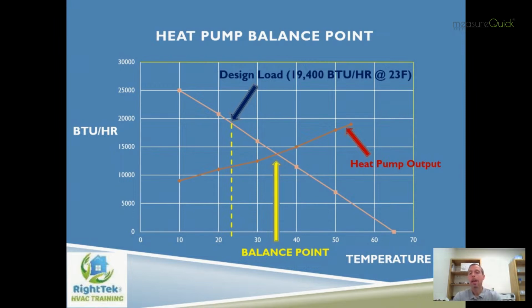But I also want to look at that heating performance. In my world, I always wanted a unit that not only fell within the sizing parameters given to me on the cooling side, but also would carry that home down on the heating side, preferably into at least the middle 30-ish range. Then I knew I would have a heat pump that was going to perform reasonably well and efficiently for both heating and cooling that house. And as Jeremy mentioned earlier, I really want to minimize the need and use of any unnecessary excessive heat strips.